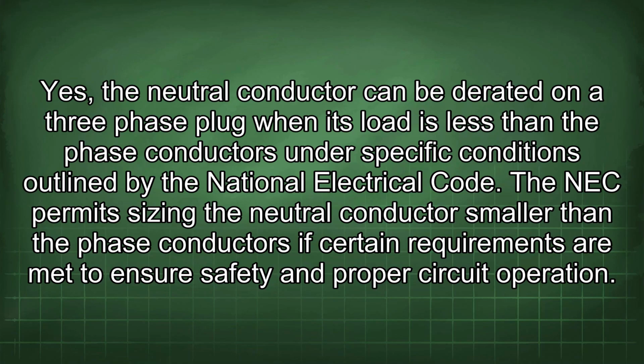Yes, the neutral conductor can be derated on a 3-phase plug when its load is less than the phase conductors under specific conditions outlined by the National Electrical Code. The NEC permits sizing the neutral conductor smaller than the phase conductors if certain requirements are met to ensure safety and proper circuit operation.